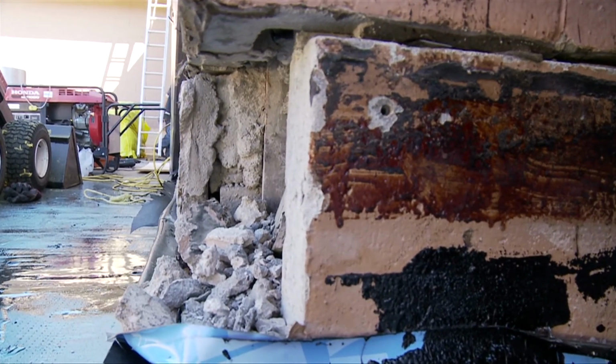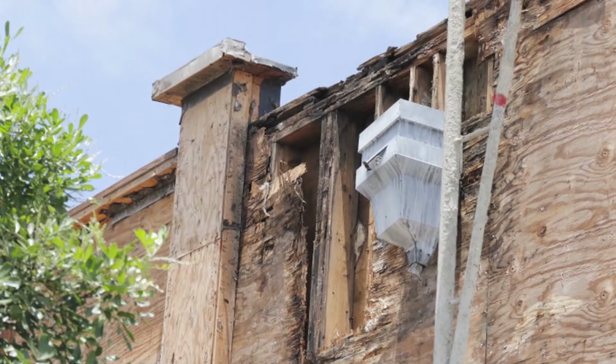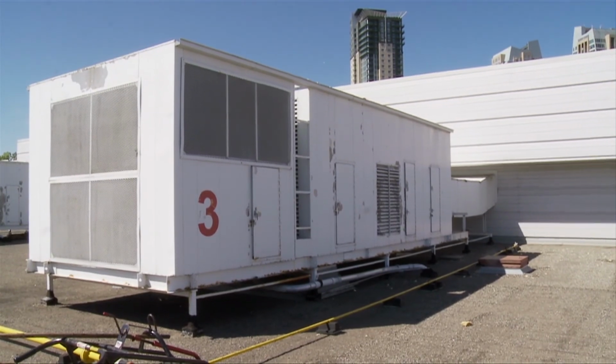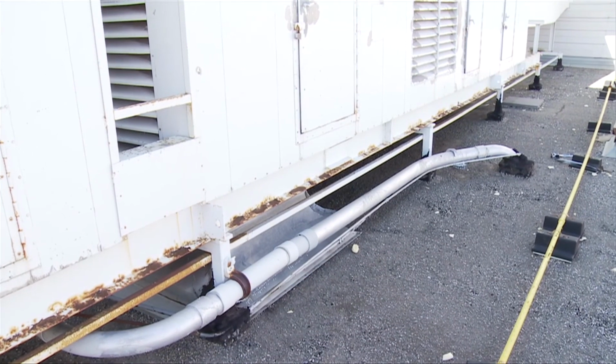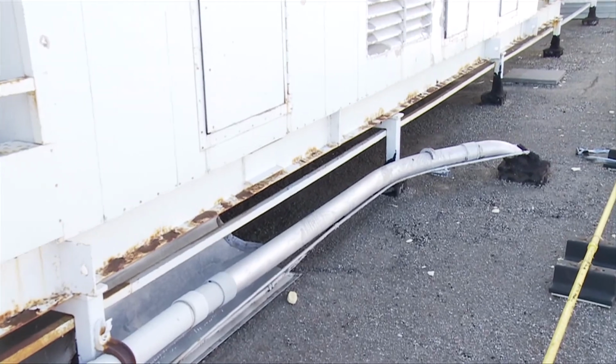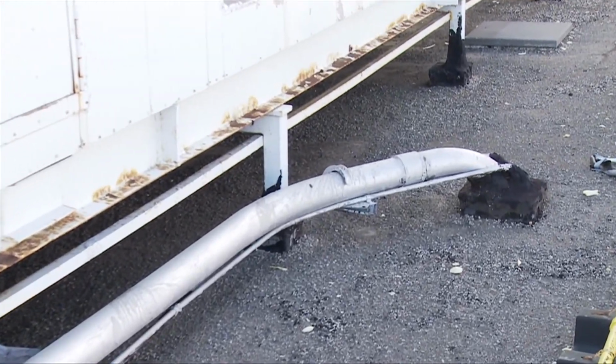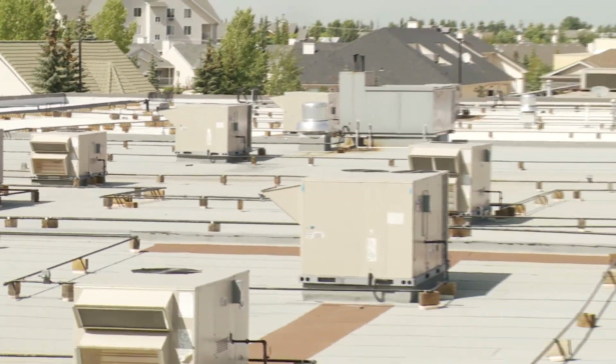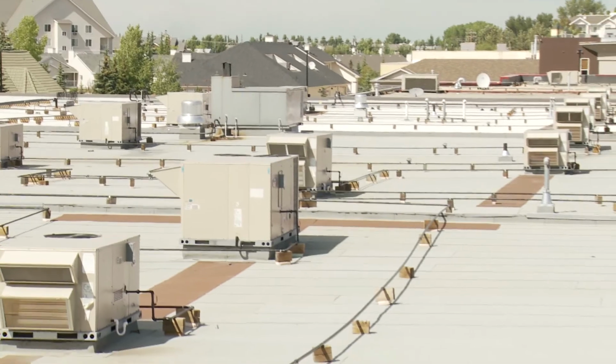Accumulations of dust and other combustible materials are present in parapets and wall cavities. Combustible wall finishes, such as the presence of wood siding, wood chip insulation in older buildings, and building paper behind stucco, are definitely a hazard that needs to be identified and controlled. Operational roof-mounted mechanical equipment and service lines encountered, such as heating, ventilating, and air conditioning units, intake and exhaust ventilators, gas and electrical service lines need to be disconnected or removed whenever possible.